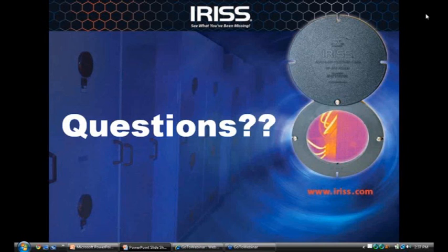A common question I get asked by customers: you'll have an 8-foot by 4-foot cabinet, and for years they were opening the doors and scanning the whole cabinet, and their thing is, well, I can't put an infrared window or an ultrasound in there because I can't see the whole cabinet. The relevant question to ask is, what do you want to see inside that cabinet? I don't really want to be looking at all the bus and the cable. I want to look where all this stuff is bolted together.